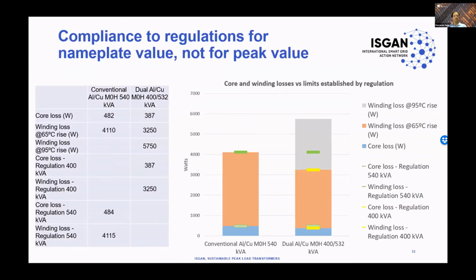So for this, we have prepared here the graphs for a conventional unit, which is sized, as in the example before, 540 kVA, and then a dual nameplate or sustainable peak unit, which is rated to 400 at 65 degrees, but 532 at 95 degrees. So basically, in terms of peak load capacity, both are comparable.